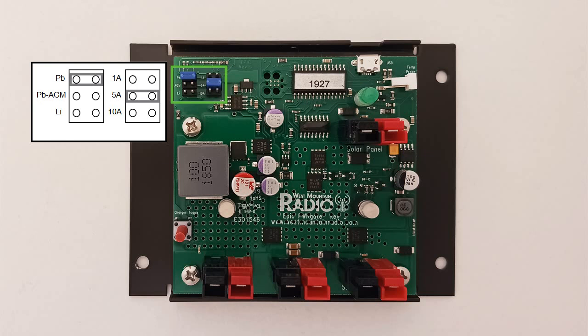Lithium iron phosphate batteries usually use the amp-hour rating; some specify 50% to be safe, or others may specify being able to handle double. The jumper selection shown would be correct for a gel lead-acid battery that is 50 amp-hours. This is the standard configuration for the PWRgate.